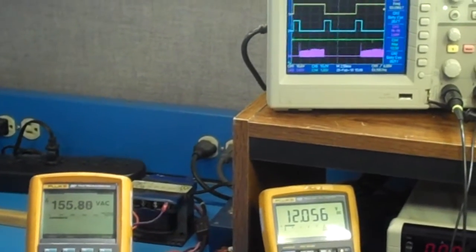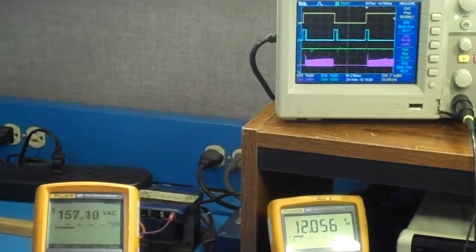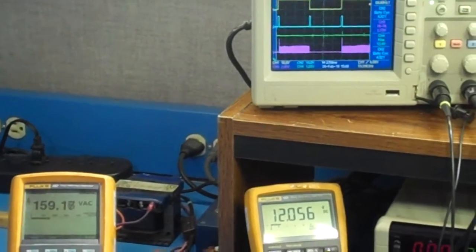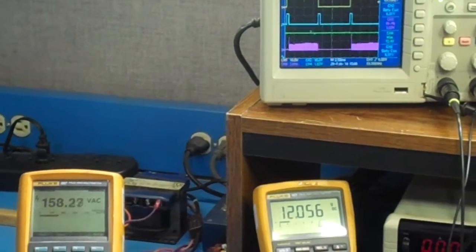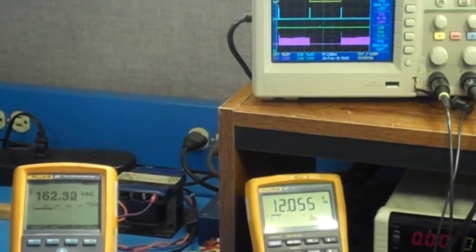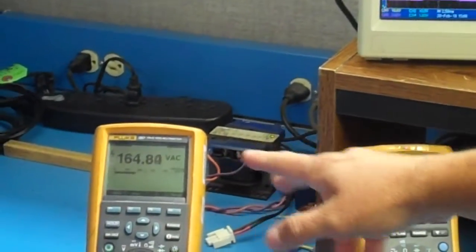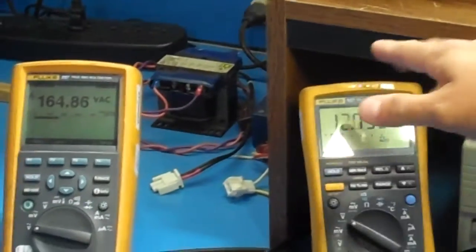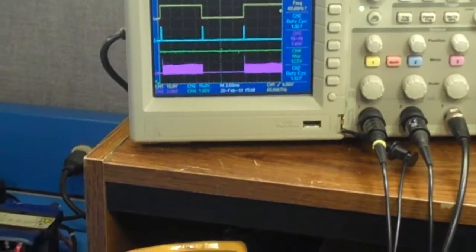Alright, right about there. You want to see if you can find that spot. Right now we're at 155. Alright, just bring it to 160, 165. We're at approximately 164, 160 volts AC. Everything's okay. Tony, you can go ahead and drop it below 160.